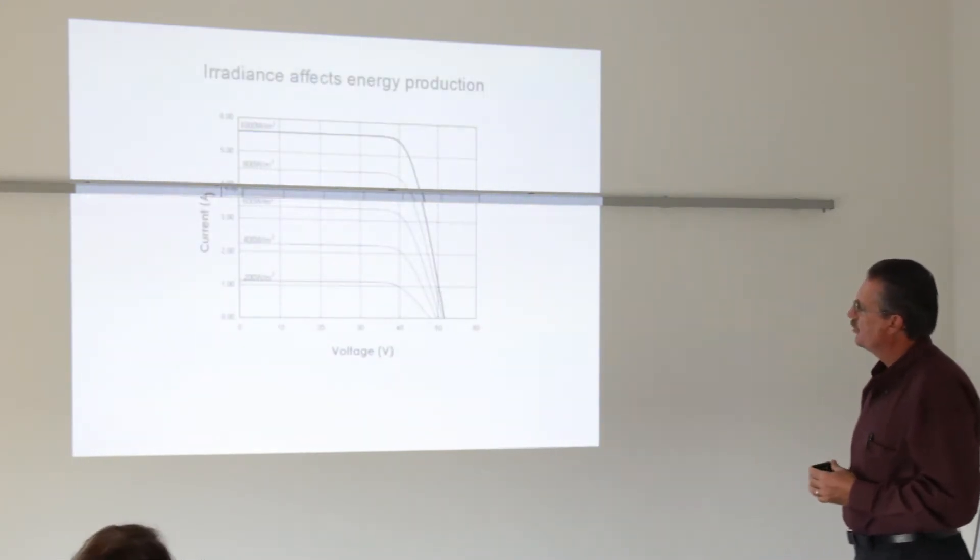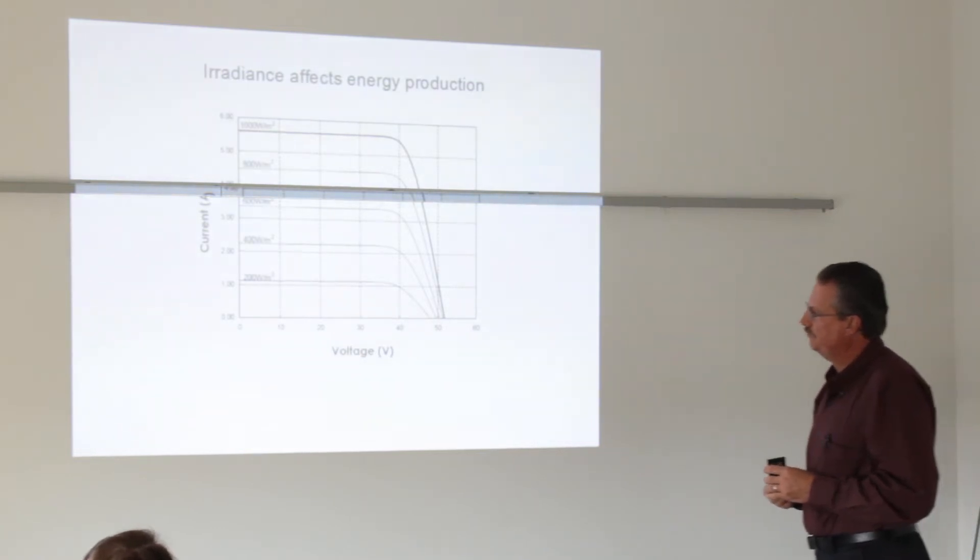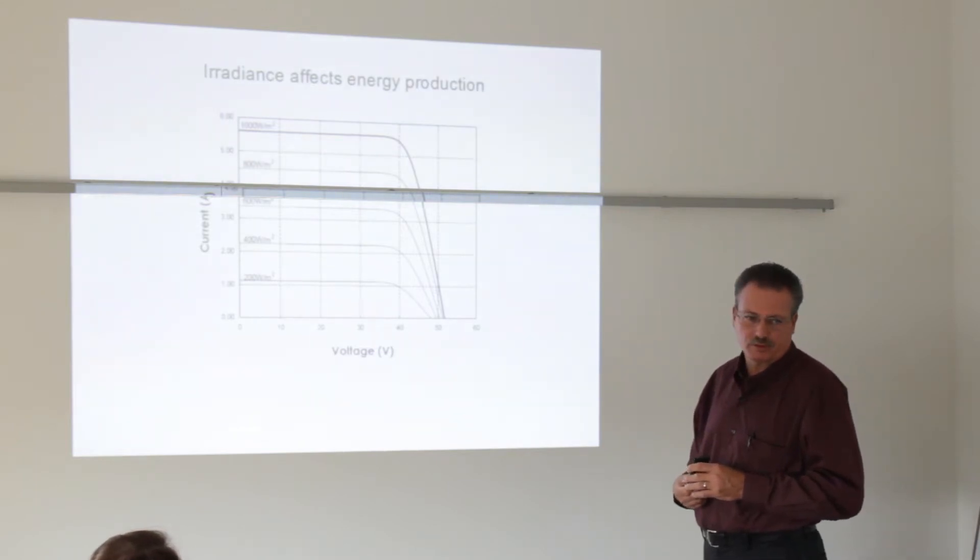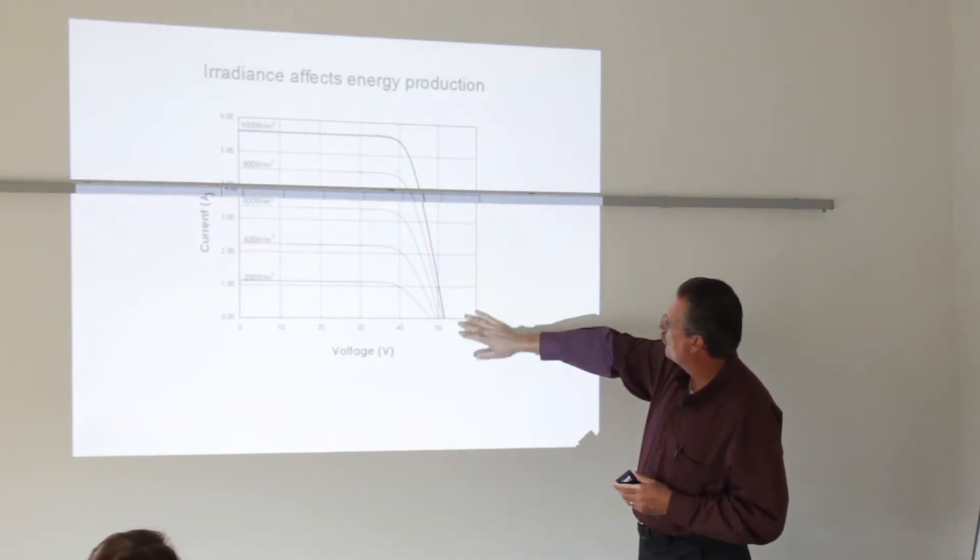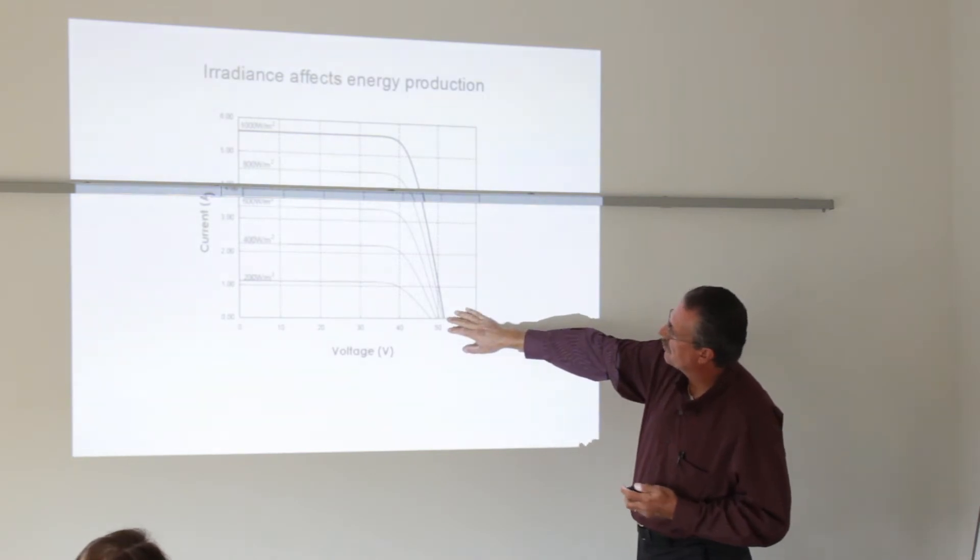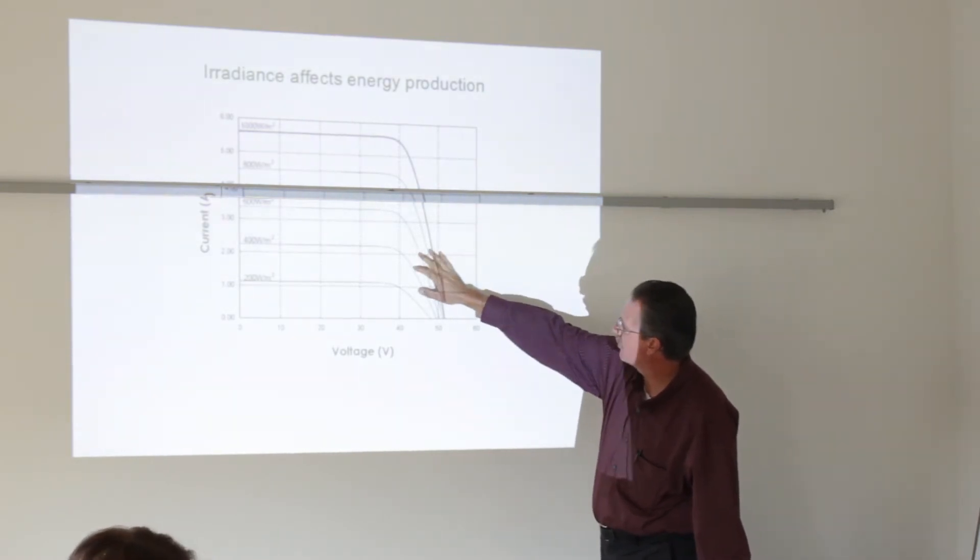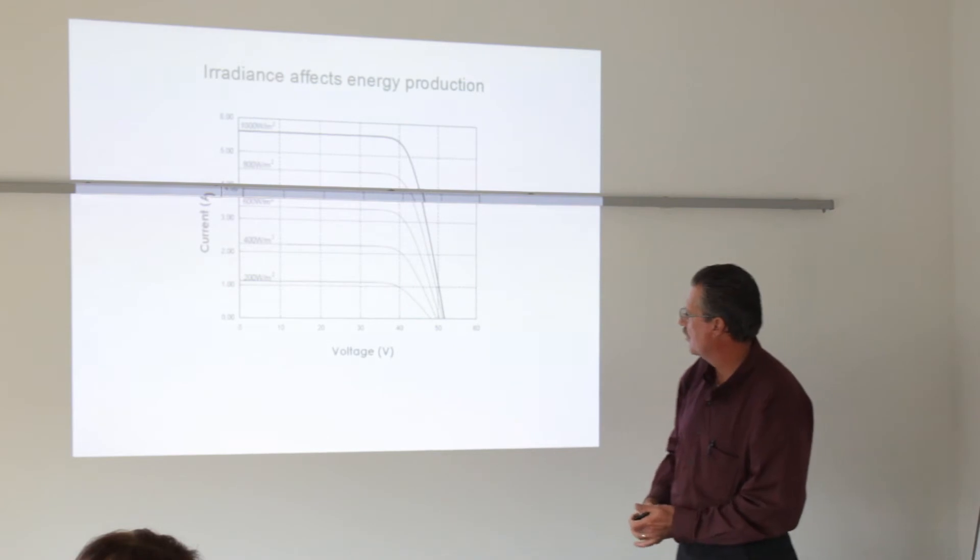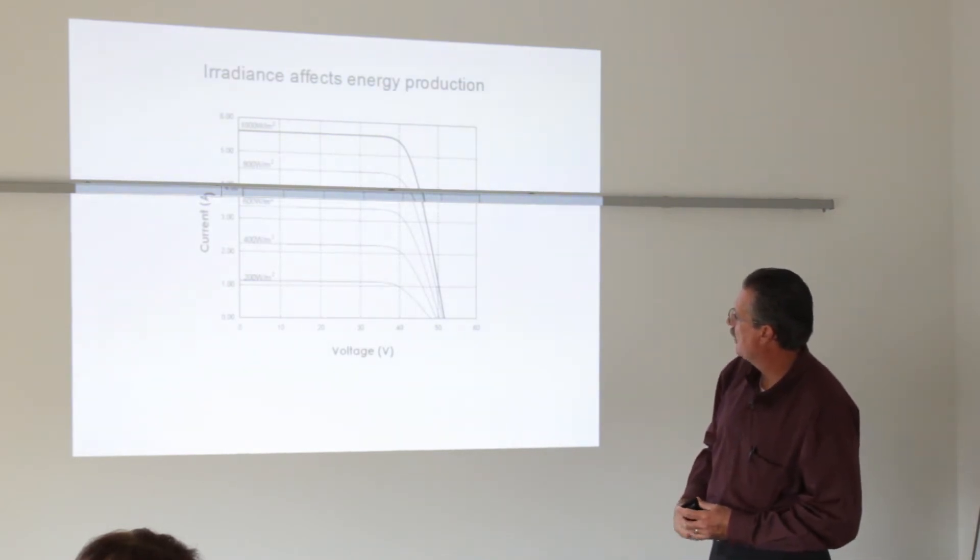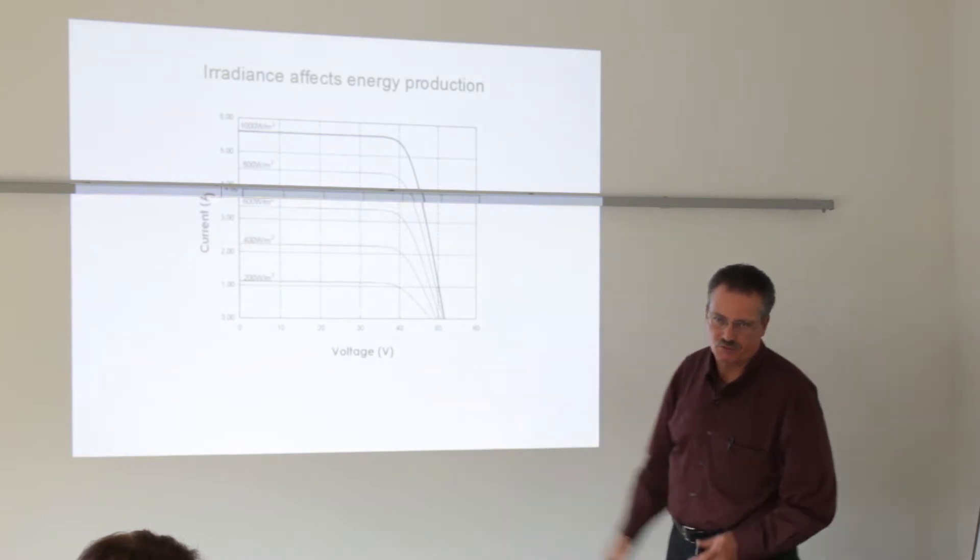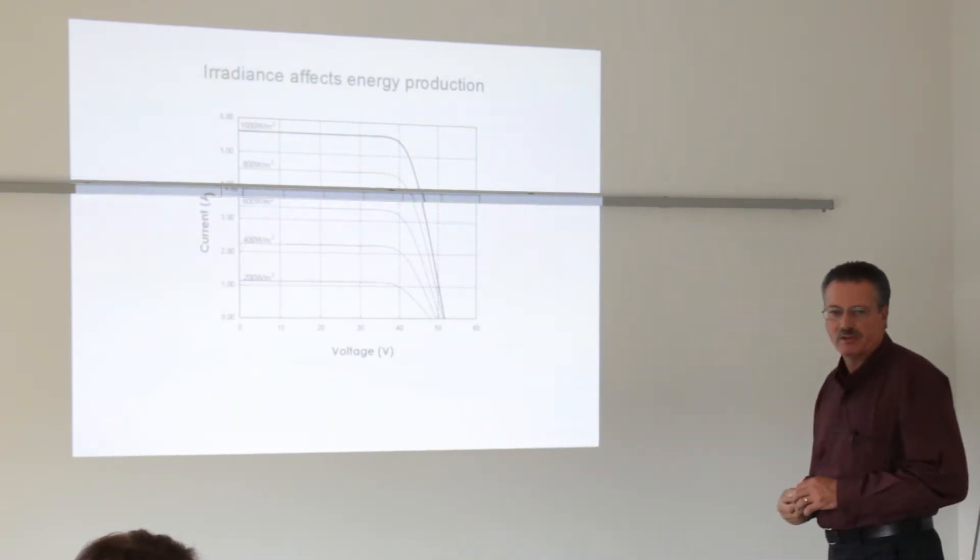Irradiance affects energy production. Just because it may be a little bit cloudy doesn't mean things stop working, they just don't work as well. Notice our top line, which is our standard 1,000 watts per square meter. But if you drop down to 800, which is what we see on average, or 600, 400, 200 watts per square meter, you'll see a reduction in energy production, but you don't see it stop. You still have energy production even on a cloudy day.